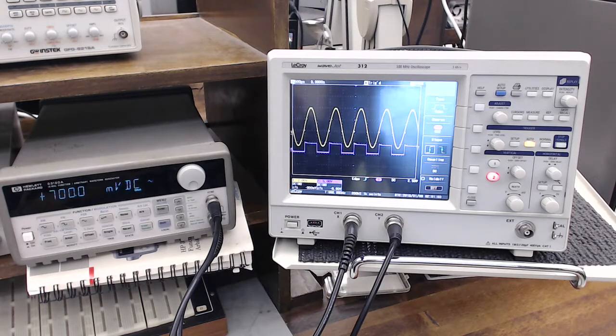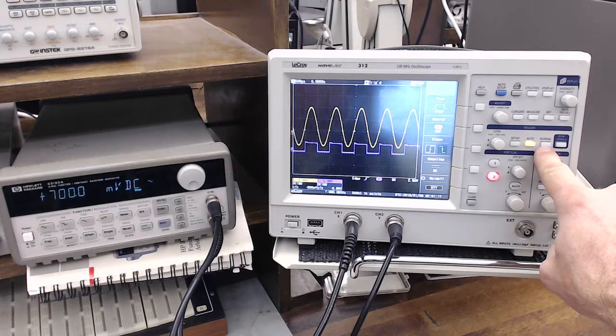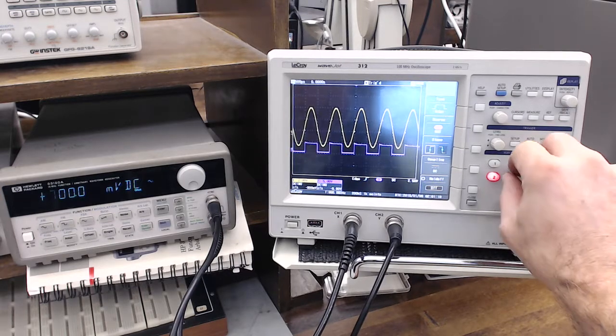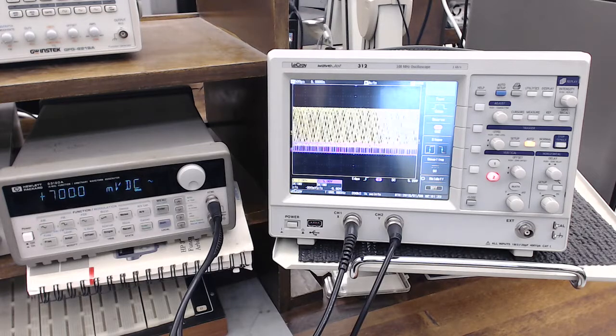With all that said, what are we going to do next? The next thing we're going to do is think about the modes of triggering. There are two modes that one usually uses. One is auto and one is normal. The auto one is the one that can get confused as you go like this, because if it doesn't see a regular trigger, then after a certain delay it just chooses to let the waveform go across the screen anyway.